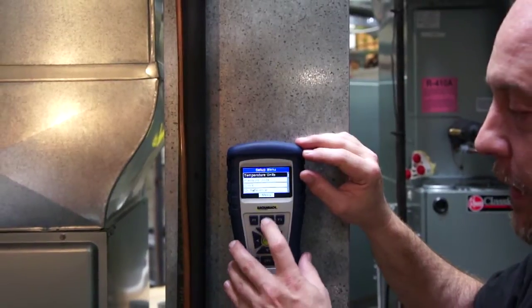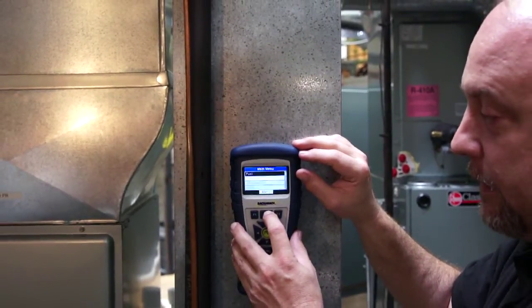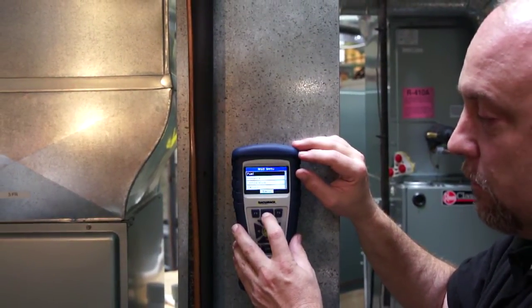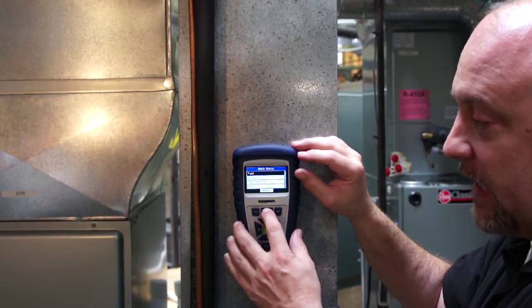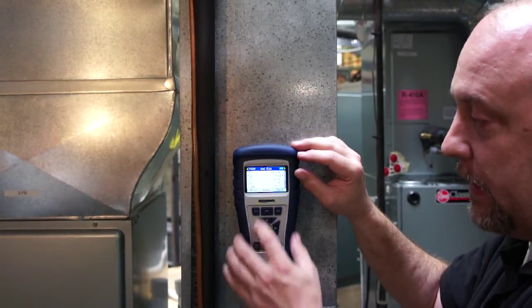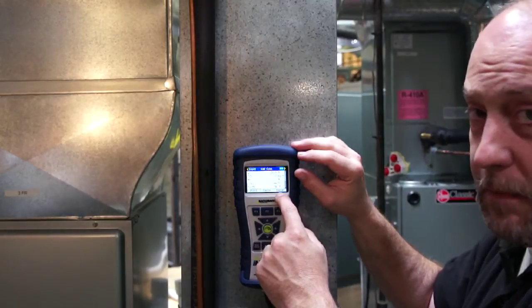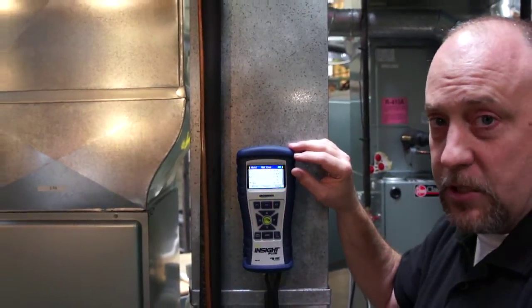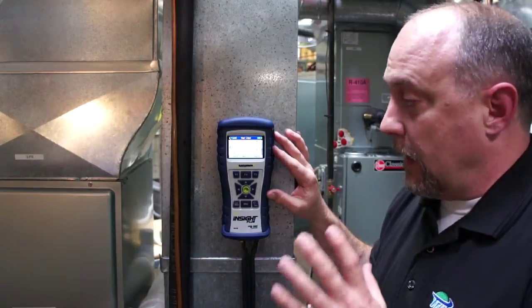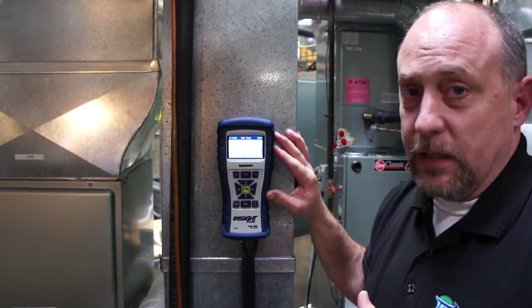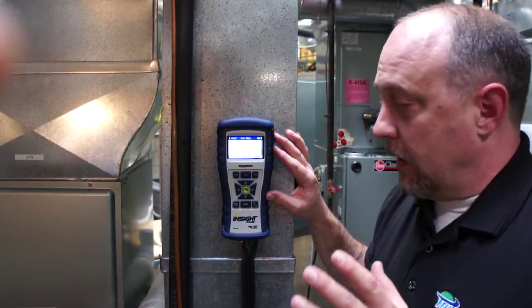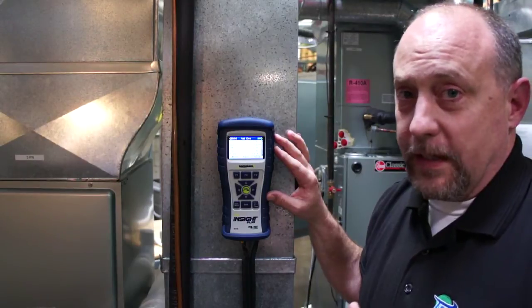I'm going to hit enter, and then I hit the menu key right here again. It's going to take me back to the fuel menu. And if I hit it again, you'll see it's not going to do anything until I press the run hold key, and that's going to take me back into my measurement menu where I can actually start doing my combustion test. Earlier I was talking about how user configurable the Insight Plus is, and I really wanted to show you some of the things that we can do with this to make it work exactly the way we want it to work.